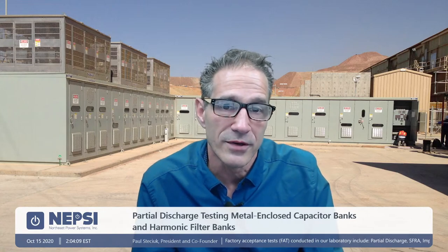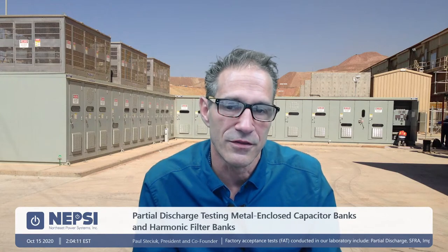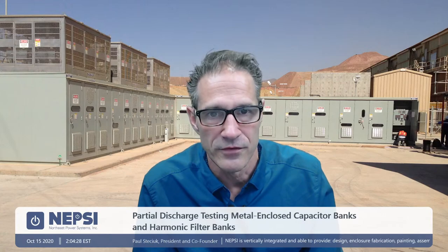So today we're talking about partial discharge testing. It's a third very important factory acceptance test that we do here at NEPSI. And partial discharge is very important because it speaks to the life of the equipment rather than just the design of the equipment.